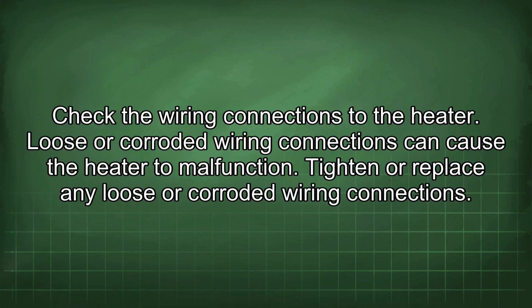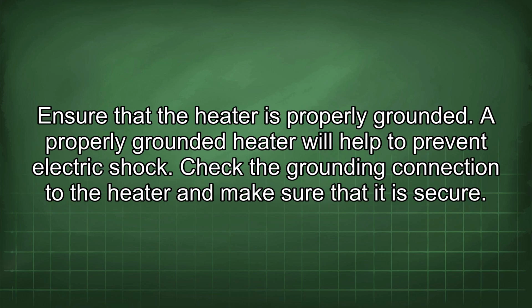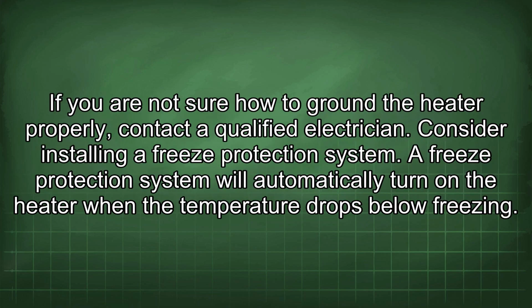Check the wiring connections to the heater. Loose or corroded wiring connections can cause the heater to malfunction. Tighten or replace any loose or corroded wiring connections. Ensure that the heater is properly grounded. A properly grounded heater will help to prevent electric shock. Check the grounding connection to the heater and make sure that it is secure. If you are not sure how to ground the heater properly, contact a qualified electrician.